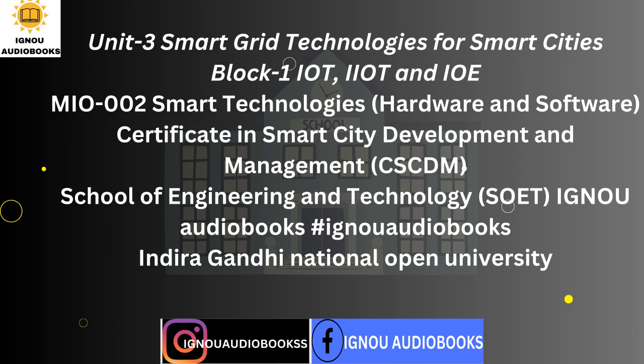restoration of the faulty part. Outage management systems manage outages by way of manual intervention, self-healing and maintenance crew management. Continuous monitoring of the system helps in being proactive. Whenever a fault takes place, the following information shall reach the control center. A. Location of fault through FPI. FPI in the faulty section will operate due to high fault conditions.